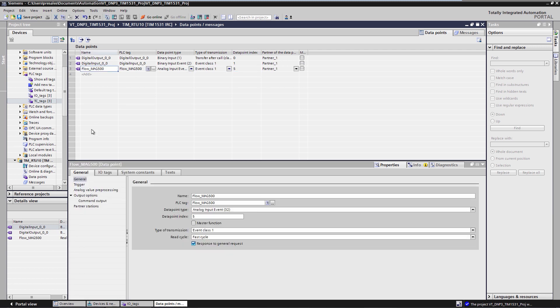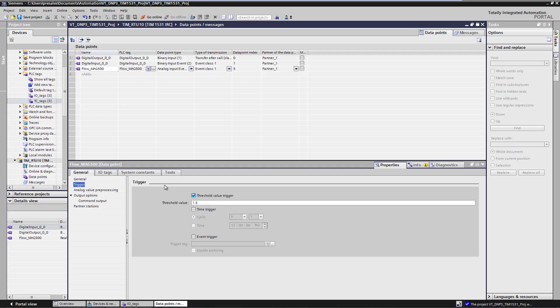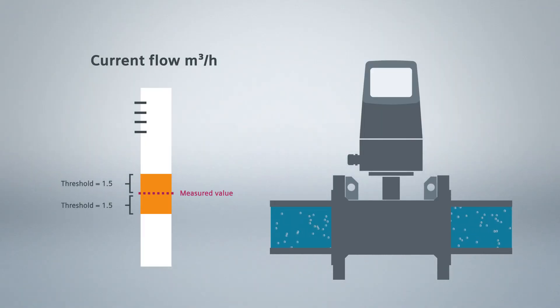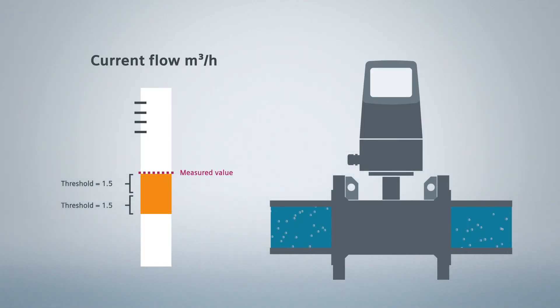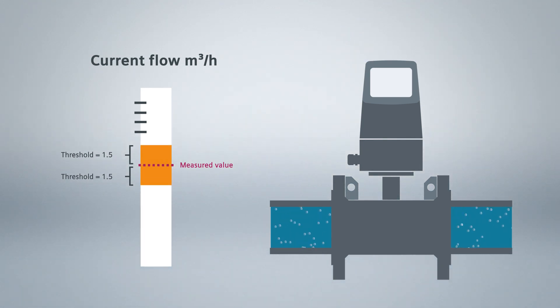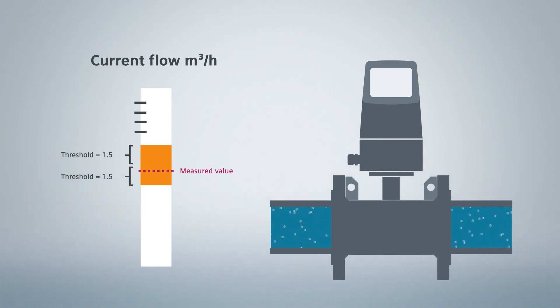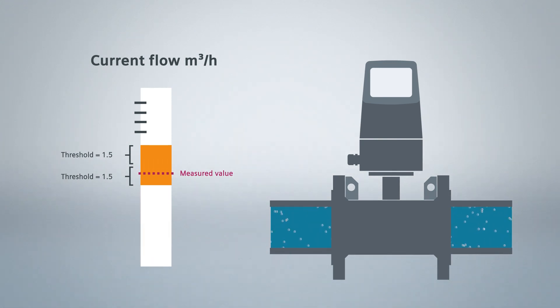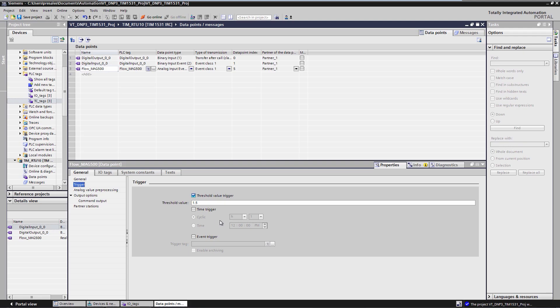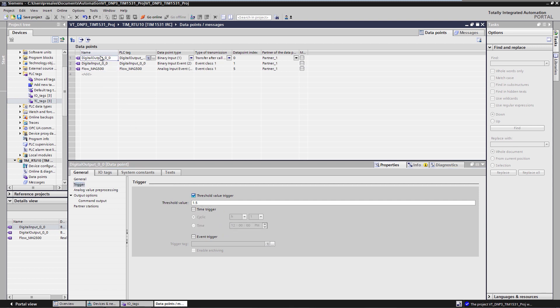For the measured value, we still need to define the appropriate threshold value. Only if the measured value experiences a change greater than the threshold value, it will be transmitted to the control center. This ensures that not every small change triggers a transmission and thus prevents unnecessary load on the communication route. We could, of course, also choose other criteria such as cyclic data transmission or combined transmission criteria.